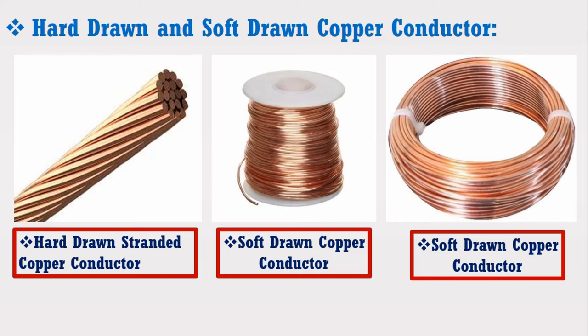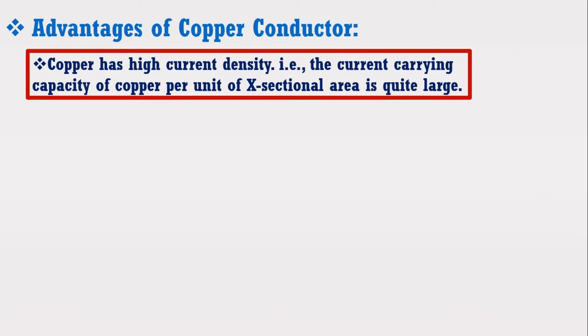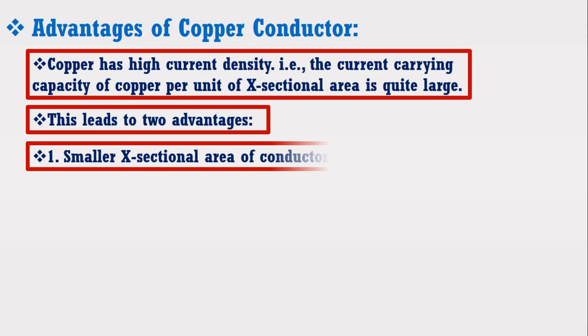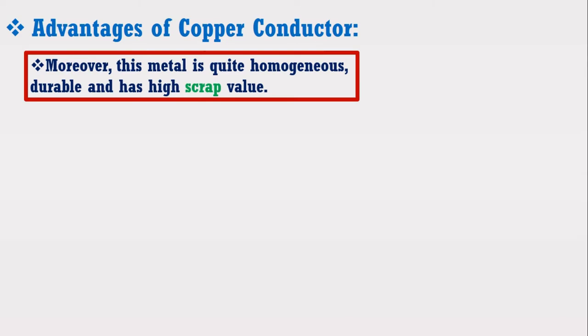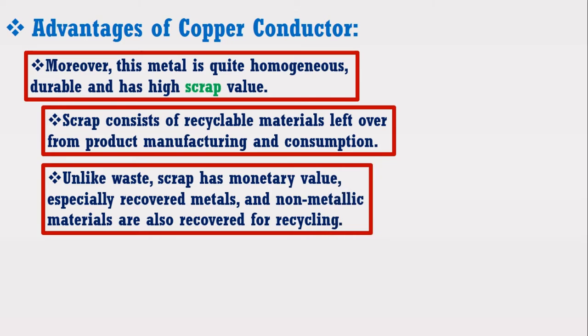The figure shows the hard drawn and soft drawn copper conductor materials. The advantages of copper conductor include: high current density, meaning the current carrying capacity of copper per unit of cross-sectional area is quite large. This leads to two advantages: 1. A smaller cross-sectional area of conductor is required, and 2. The area offered by the conductor to wind loads is reduced. Moreover, this metal is quite homogeneous, durable, and has high scrap value. Scrap consists of recyclable materials left over from product manufacturing, and unlike waste, scrap has monetary value.